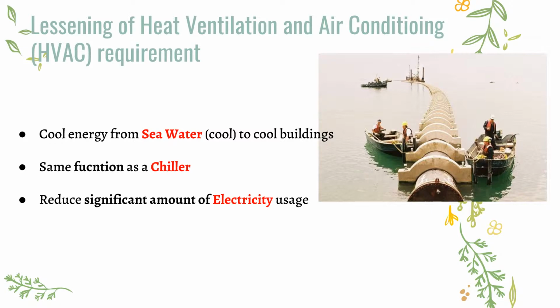Deep water cooling system can reduce the use of electricity in the air conditioning system. The fundamental concept is using cool seawater to provide cooling energy to the heat exchanger, therefore providing chilled water to cool the buildings. It replaces the need for chillers at the customer's site, and most importantly, cuts off the large amount of electricity needed to support chillers for air conditioning.